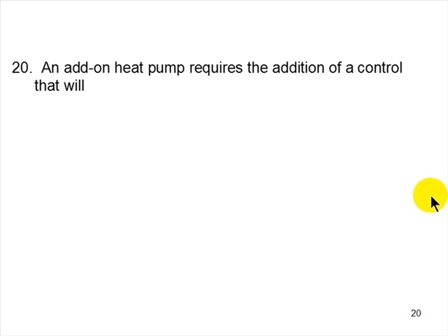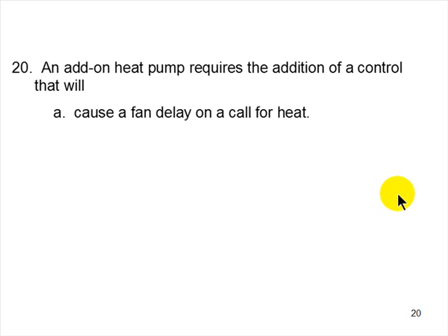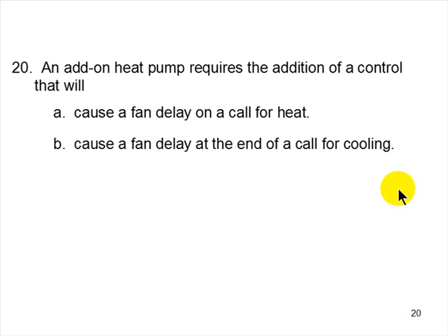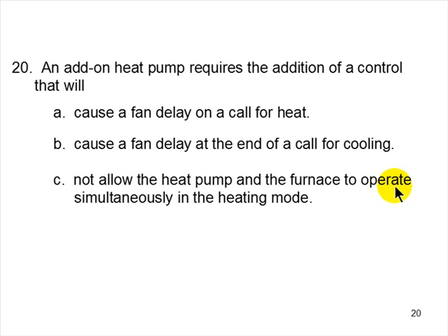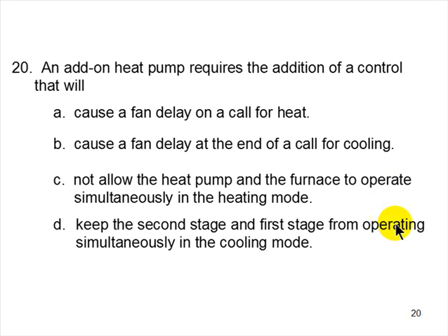20. An add-on heat pump requires the addition of a control that will cause a fan delay on a call for heat, cause a fan delay at the end of a call for cooling, not allow the heat pump and the furnace to operate simultaneously in the heating mode, or keep the second stage and first stage from operating simultaneously in the cooling mode.